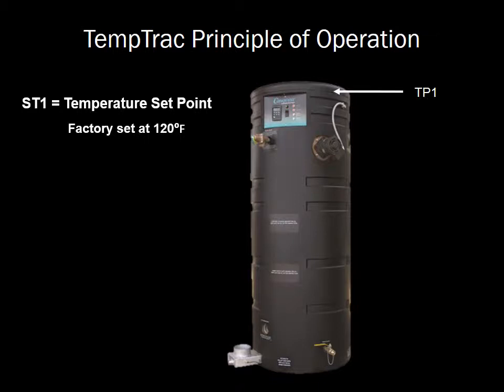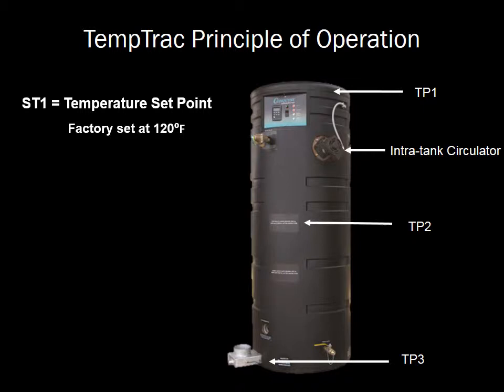Temperature probe 1, TP1, is located at the top of the tank near the hot water outlet and serves as the primary water temperature control for the Temptrac. Temperature probe 2, TP2, is located in the middle of the tank and is used to anticipate changes in the stored water temperature and cycles the intra-tank circulating pump to ensure a more consistent hot outlet temperature. Temperature probe 3, TP3, is located in the vent connection and monitors the flue gas temperature.